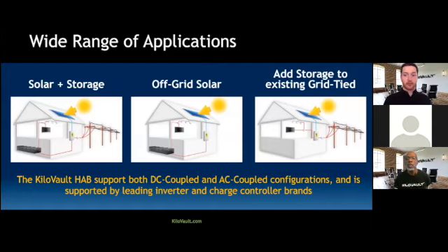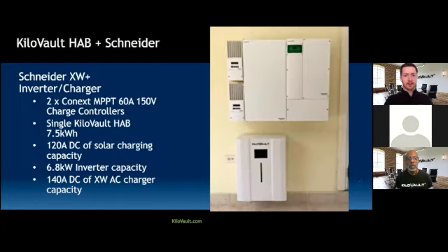And as I've kind of alluded to, these batteries really can be used in any sort of system, whether it's a grid-tied battery backup, a totally off-grid system, an AC-coupled system where we're adding battery storage to an existing grid-tied setup. The batteries don't really care as long as the charge controllers and inverters are programmed accordingly. And that's something we wanted to highlight here, where we really wanted this battery to be inverter agnostic. As I mentioned at the beginning, it is a 48 volt battery, so you need a 48 volt inverter. But we support just about all of the major inverter brands on the market.